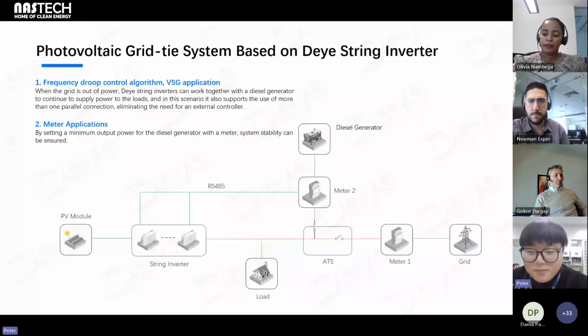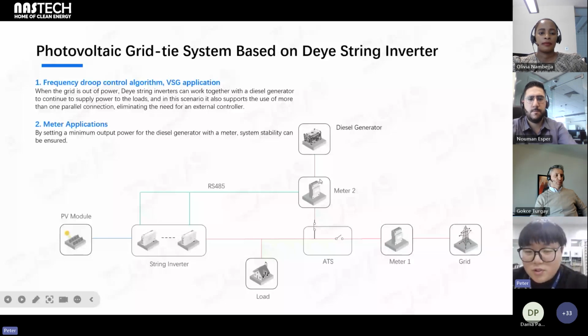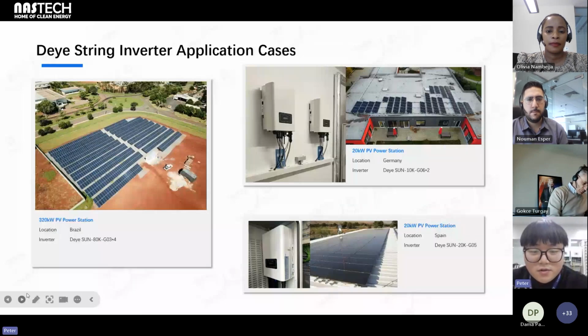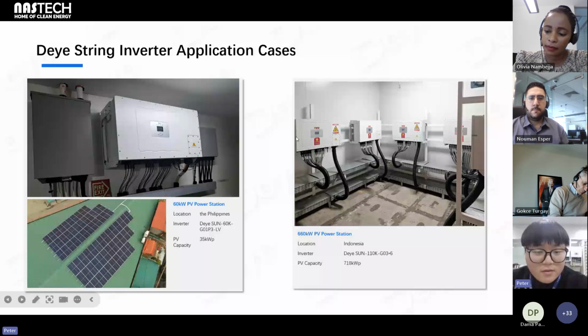And our string inverter now is from 1 to 136 kilowatt. And we have a solution where you can run your string inverter off grid. And we can use a diesel generator. With an external ATS device, you can switch to the diesel generator side when the grid is off. And in this case, meter 2 on the generator side can measure the generator output, and can also do the zero export, just in case power feeds back to the generator. So we can use a meter to limit the export. And we can also set a minimum output power for the diesel generator, so that the system can work stably. And we also have some pictures of string inverter cases. And these are the 136K, the biggest size for now.